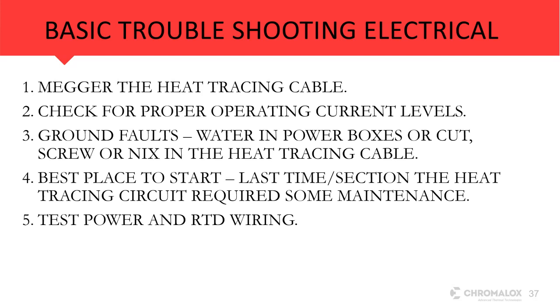We stripped off the insulation, we redid some piping, we put some insulation back on, and the insulator shot a screw into the heat tracing. So now we've got a ground fault situation there. Another reason why you may have a breaker tripping is we've taken an existing circuit and added on some heat tracing to that, and now we're exceeding what the circuit breaker is capable of handling. That's why I like to take those ISOs and update your circuits, and make sure that someone doesn't just go and add something on, and now I've got a case where I'm drawing too much current on startup, or too much current on steady state, and my breaker's tripping all the time.